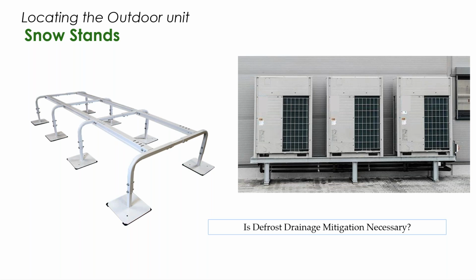First and foremost, one thing that should never be left out in cold climate, anywhere that we get snow, and typically where it gets cold, is that you want to make sure that you have variable refrigerant systems put up onto a stand, whether that be a manufacturer supplied accessory, third-party option, or something that you have field fabricated. Every manufacturer's guidelines are pretty similar, that you want to plan to have good clearance above any expected snow or drift for the region that you're working in.